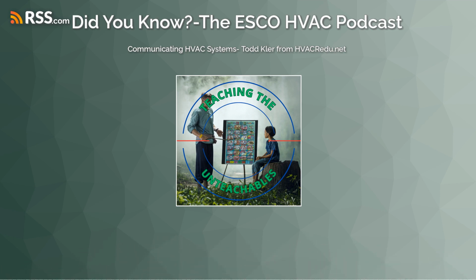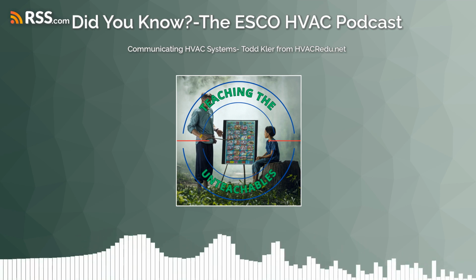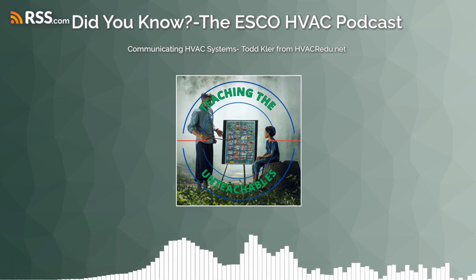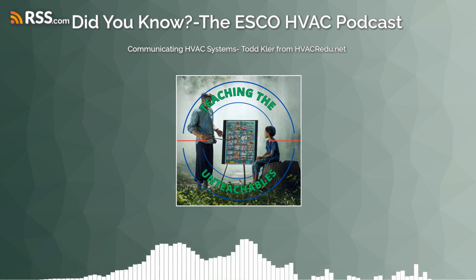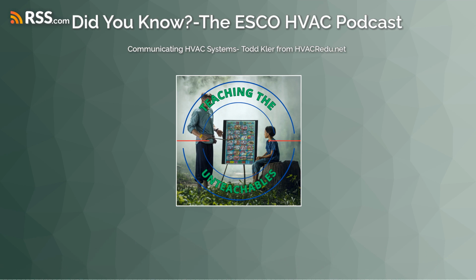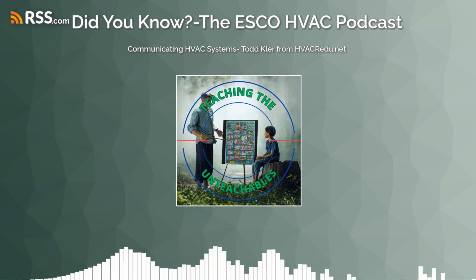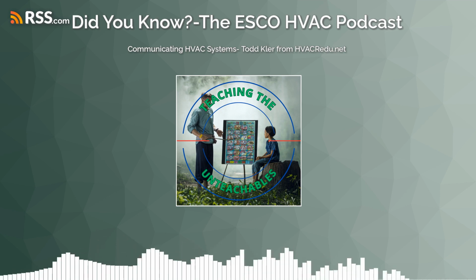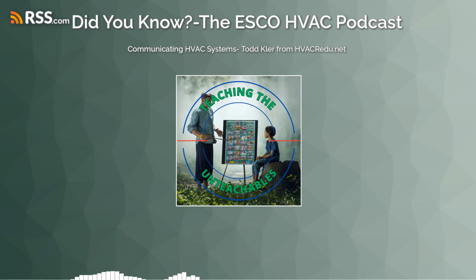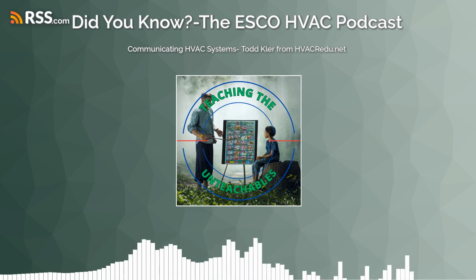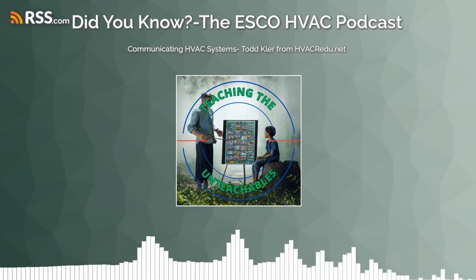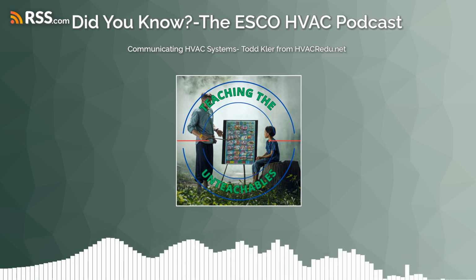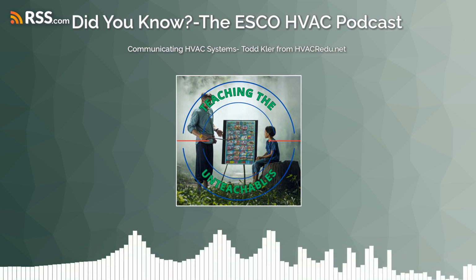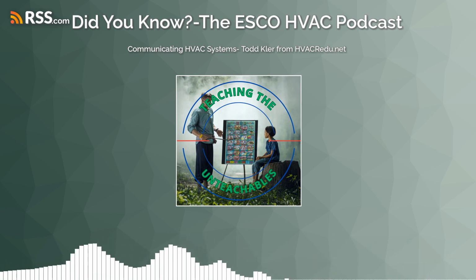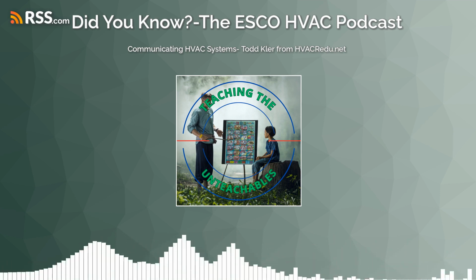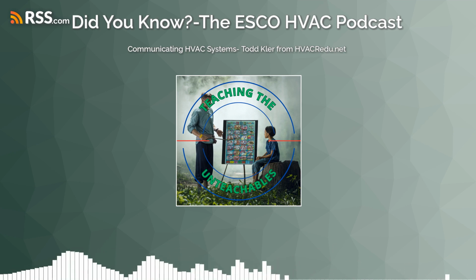I wonder what those are. Right. So as elusive as these may seem, they're really not. One difference that we do see with this particular brand is we may not be using that 24 volt AC all the time. We might have a 12 volt DC. So if we hop over to the smart hub up here, when we get to our smart hub, we originated with 24 volts AC and our 2 communicating. When we go out of our smart hub, we're actually going to now start using a DC voltage to work with, but we still have our A and B, or positive and negative.